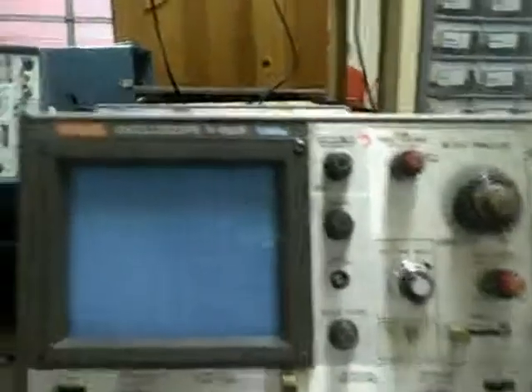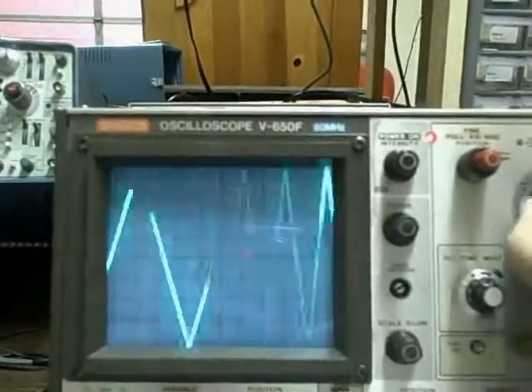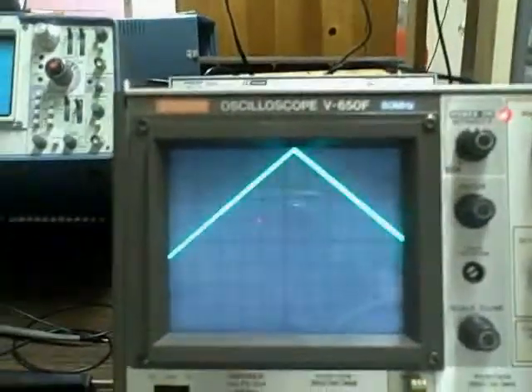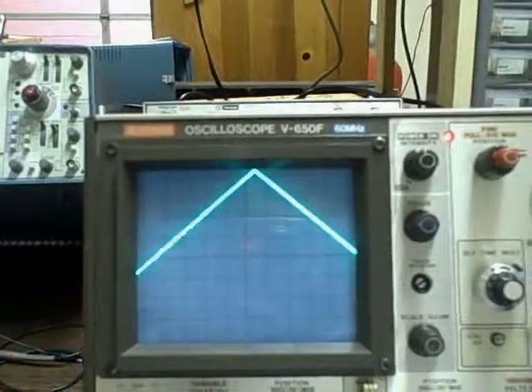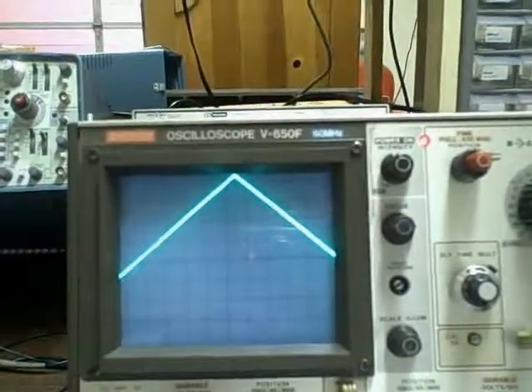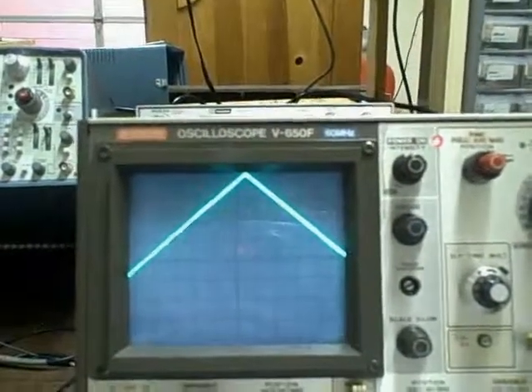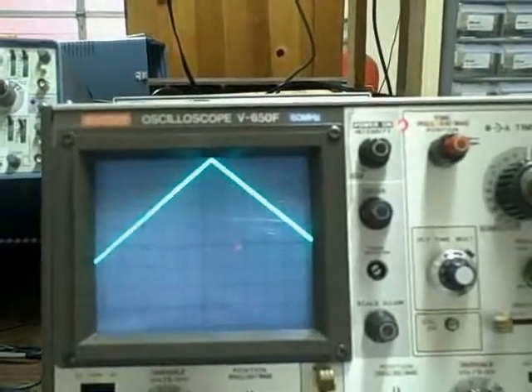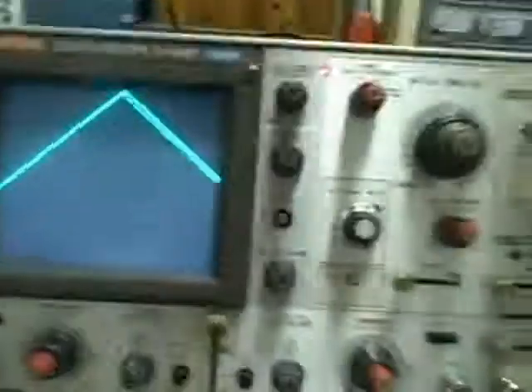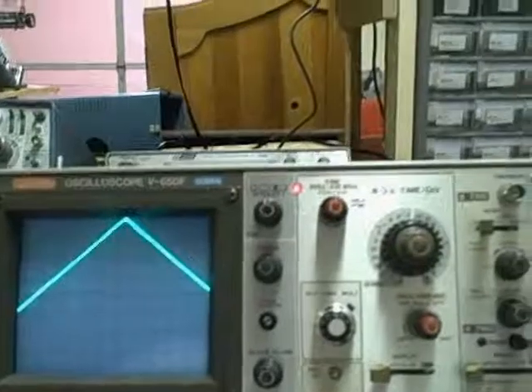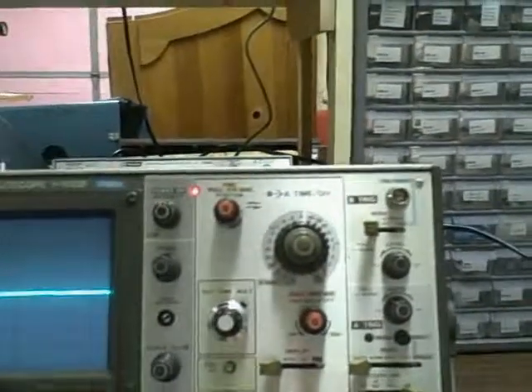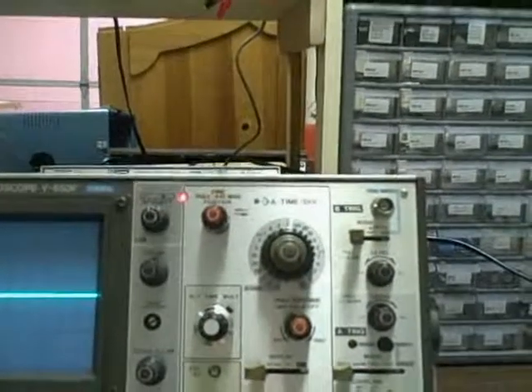But we've done it. Provided a linearity check. Our vertical scale, our time base is accurate. This scope is working, it's working very well. Now that's on Channel A, Channel 1. If I go to Channel 2... That too, this might work quite nicely on the other end. That's what we would say about our vertical scale.